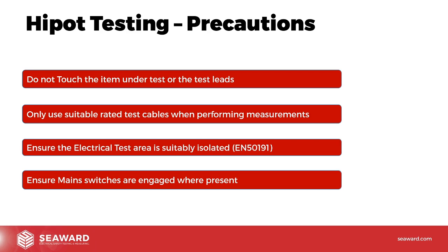Okay, so before we go any further, let's have a quick conversation about the precautions you should consider before and during the Hipot test. So first and foremost, it's imperative that we do not touch the item under test or the test leads whilst the actual test output is live. Again, this massively reduces our shock hazard. If we're not in contact with the product, we cannot be capable of getting an electric shock.